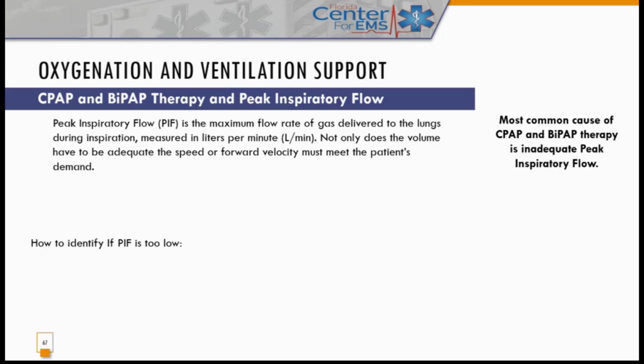So now I go ahead and I put a patient on a CPAP or BiPAP device that does not provide the air fast enough. So if you're looking at a CPAP or BiPAP device, one of the things I would ask anybody that tried to sell me one is, I want to know, what's the peak flow? How fast is the air coming to the patient? On ventilators, they have knobs that you can adjust and change the peak flow. Because if you're not giving them fast enough on the vent, they will fight you. So that's one of the important things to check, is the flow for that type thing.